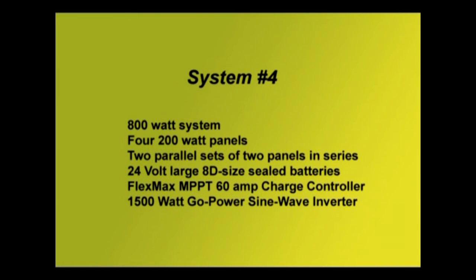System 4 is a very typical smaller system, and it's interesting to see. It's an 800 watt total system using 4 200 watt panels, wired in 2 parallel sets of 2 panels in series - so 2 in series, 2 in series - and then paralleled on a 24 volt battery system using large 8D sized sealed batteries. We're using a FlexMax MPPT 60 amp charge controller and a 1500 watt Go Power sine wave inverter.